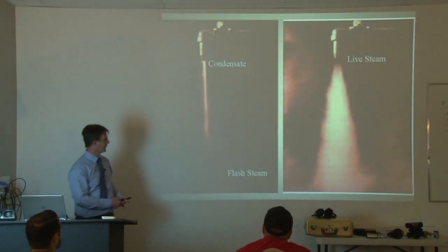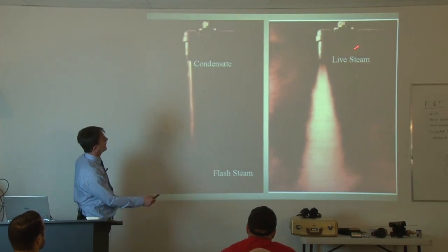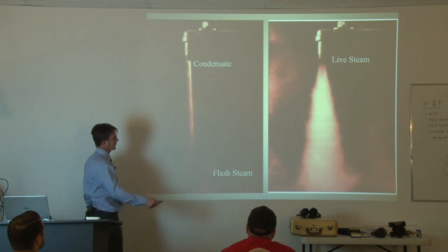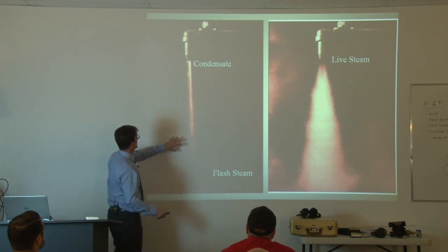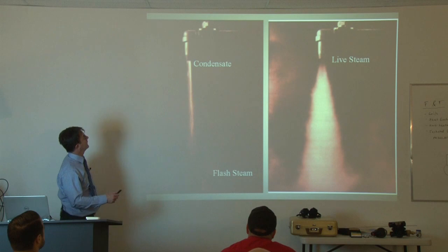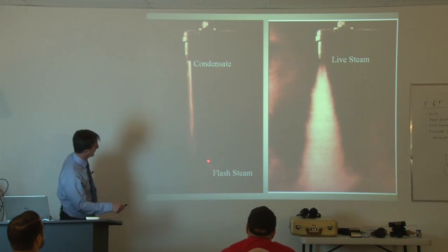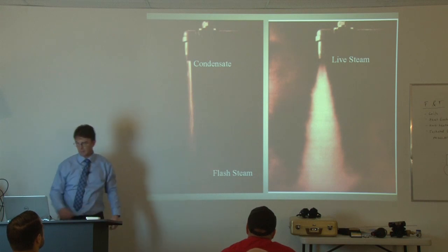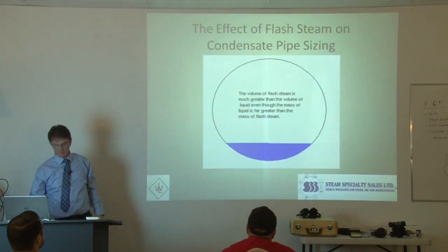So this is the difference between flash steam and live steam. The steam trap is leaking by — it's no longer holding anything, so live steam is just blasting right out. It's just a little bit of steam vapor as the trap discharges. So don't get confused between live steam and flash steam.